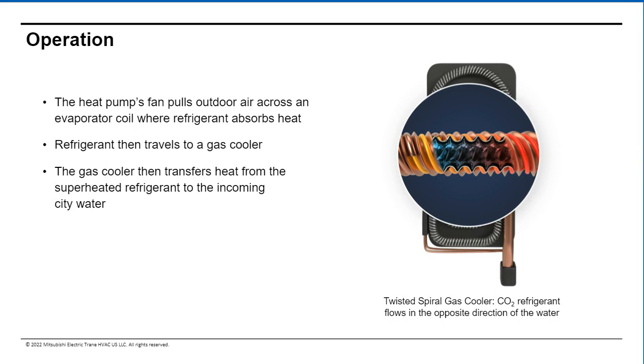So I'll look into this a little bit closer, but this is one of the cores of our technology compared to other traditional systems out there: the ability of a single pass heat pump system. What I mean by single pass is that we take the cold city water temp, let's say 50 degrees, and raise it all the way up to our storage temperature, 140, 150 degrees or higher as needed. We do that in one pass through this spiral tube heat exchanger, which is a patented heat exchanger we have on the marketplace. One of the big benefits is being able to use the CO2 refrigerant cycle to keep high efficiencies up while doing that high delta T on the water throughout the system.